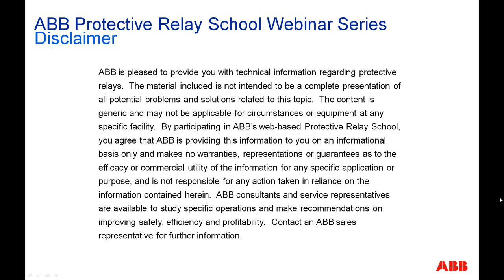Another question is line differential protection practical on MV lines such as 33 kV? Well, line differential protection can be used at any voltage level. In fact, whenever it comes to protection, it really doesn't matter at which level you are using, like line differential, or even you can use a distance protection at 33 kV as well. It only depends on what is your protection philosophy, and how much is the length of the line. If, for example, it's a very short line, then you might have only the choice of line differential, because distance protection will not work properly for a very short line. So line differential would be the only choice for you. But it all depends on what is your protection philosophy, regardless of the voltage level.